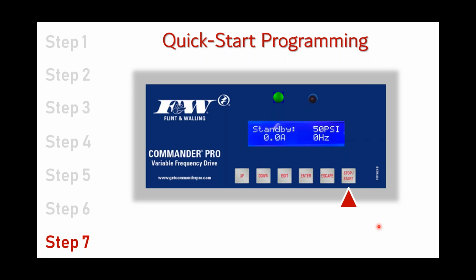And this is the other reason the contractors like a transducer over a pressure switch, because had I selected a switch, I'd have got done a little earlier because it doesn't come with those 3 sub-menus that the transducer comes with. But had I selected a switch and I come back to my home screen on a switch, all that would have been there is it would say motor in standby, 0 amps, 0 hertz, no time. Never, never, never is pressure ever displayed on the display screen.